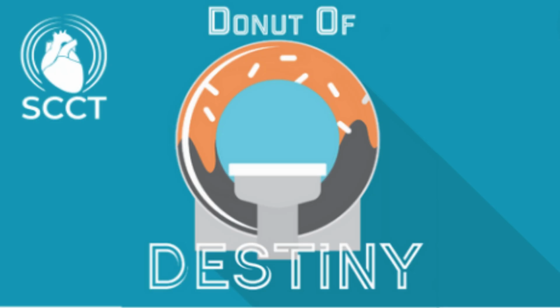And so with every one of these systems, we deliver what we call an always-on UPS system. It's a box that houses a couple of batteries. It's also where the image reconstruction system, the IRS, is housed. It's all one box, small, that's in the technical closet for the room. And it maintains power on that detector system for up to 15 minutes at a time during a power loss.